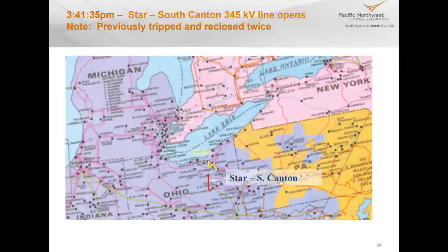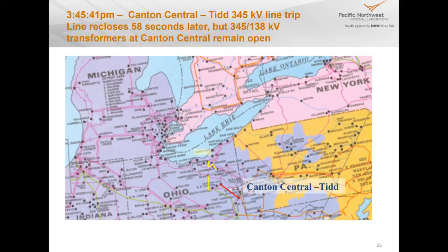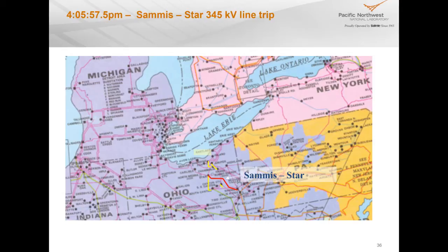So the next line that tripped, this is also a line within its rating, was at 341. And then another line that tripped, this was overloaded, but it was also tree contact. If it's overloaded, you can't blame vegetation management. And then this line at 405 was the Sammis-Star line, and this was a critical event. This is the first line that tripped not because of a fault, a short circuit, but because of getting too close to the trees, actually drawing a short circuit. This is a line that got so crazily loaded up because all of the lines around it had tripped.